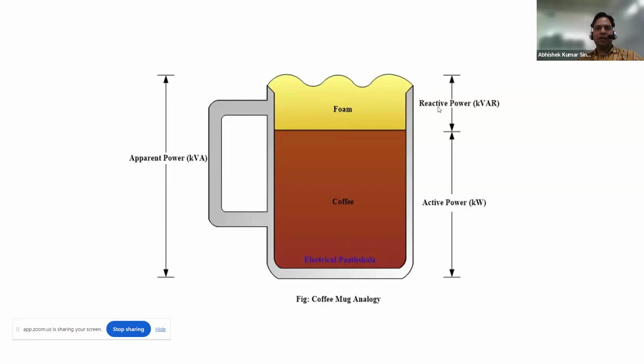If you look at LED bulbs, 0.9 or 0.95 is mentioned on the bulb. So the power factor will always be of the load, and the OEM has to decide how much it will be. But our point is that we have to control this. How will we control this? We will not take it from the source. We will inject it from the internal system through power factor panels.